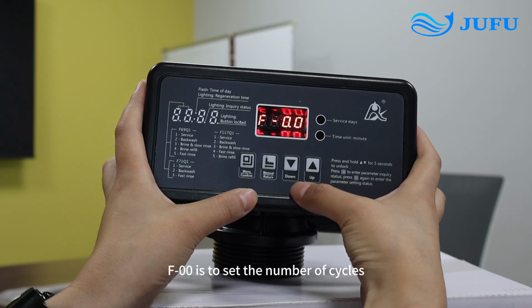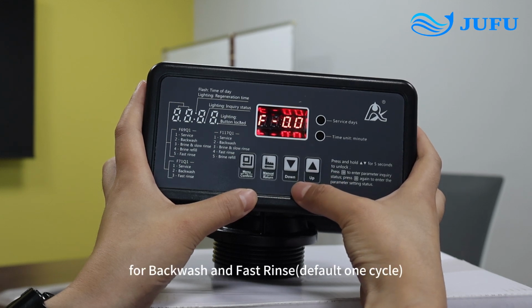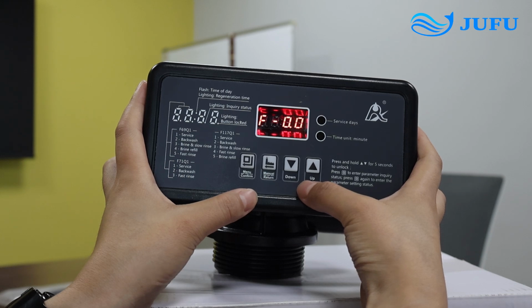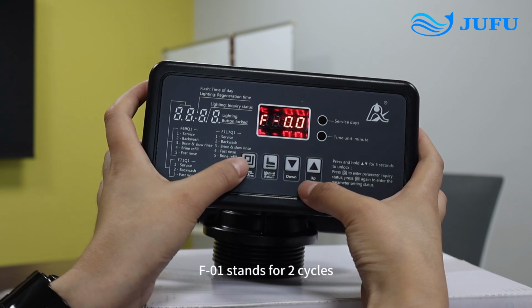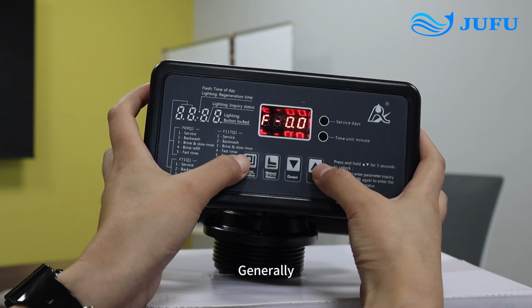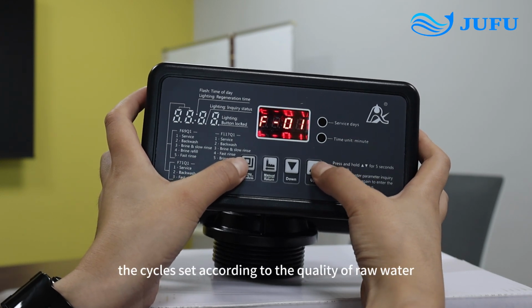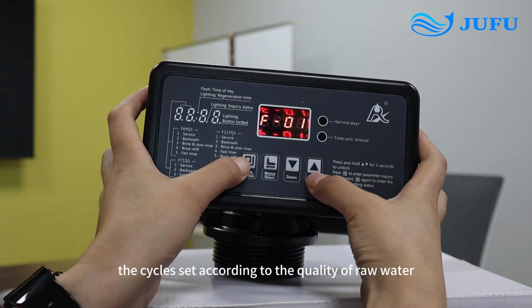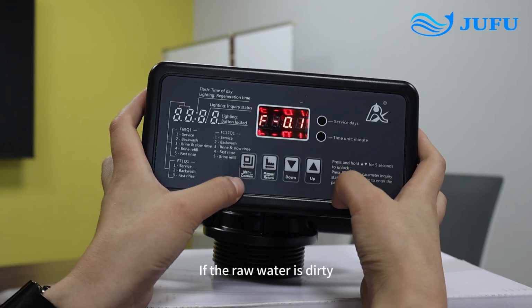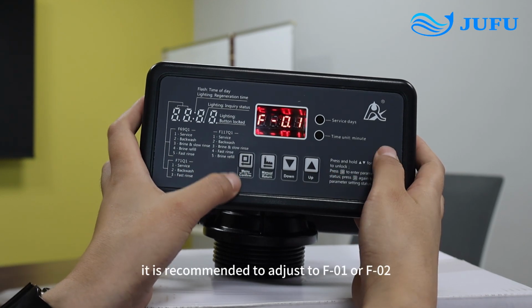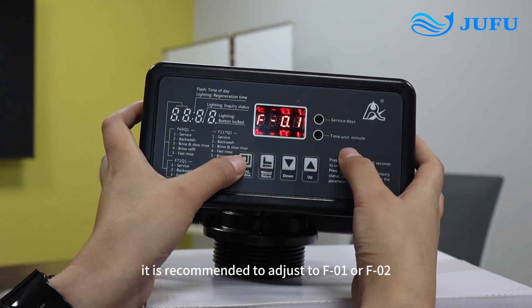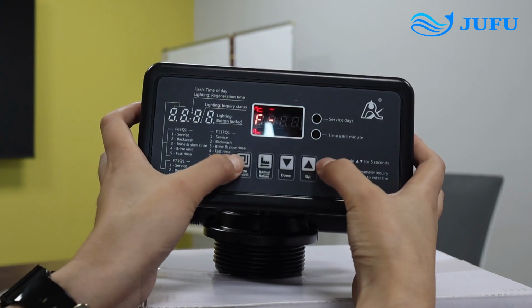F00 is to set the number of cycles for backwash and fast rinse. Default 1 cycle. F01 stands for 2 cycles. Generally, the cycle sets according to the quality of raw water. If the raw water is dirty, it's recommended to adjust to F01 or F02.